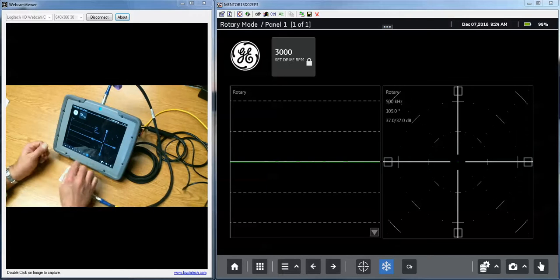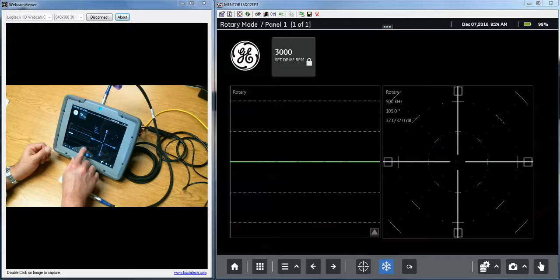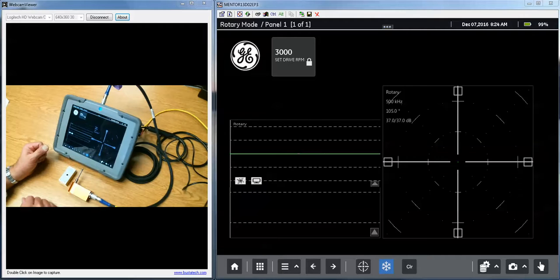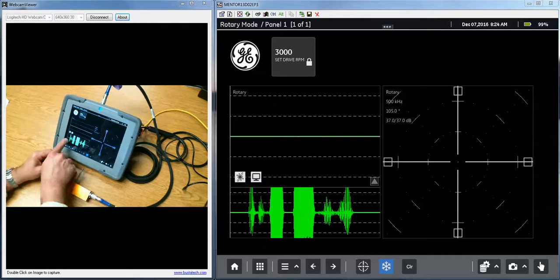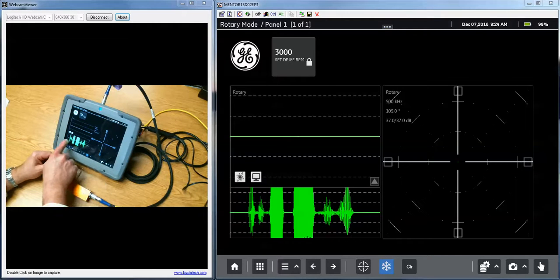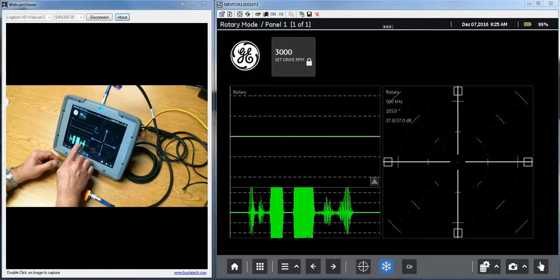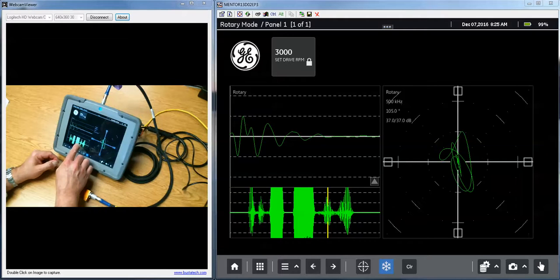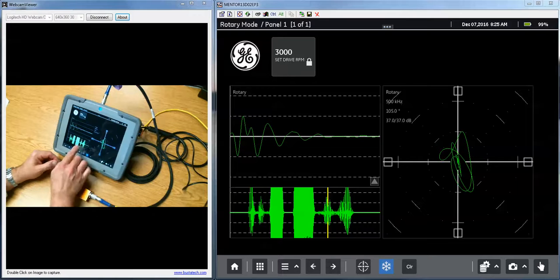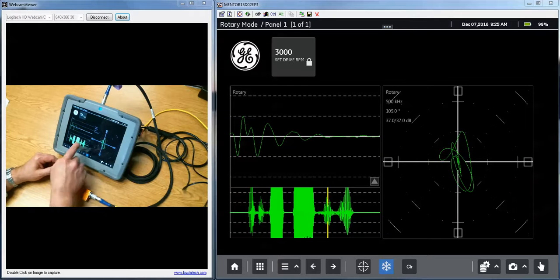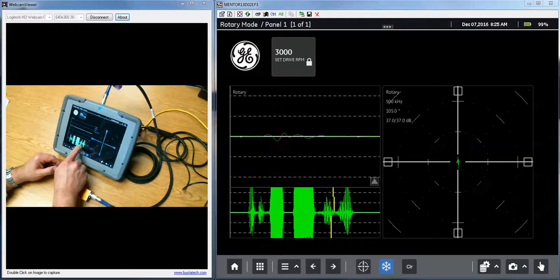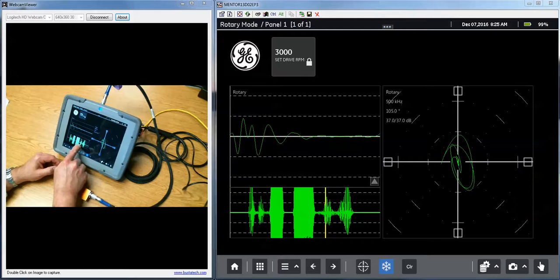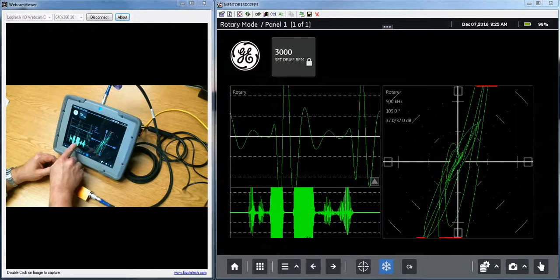Now if I open on the time-based view, I see along the bottom in my overview, I see every rotation of the probe. If I put a cursor down, the cursor is automatically set to be exactly one rotation of the probe wide. And whatever the probe was seeing during that rotation is what is displayed on the time-based view on the top.